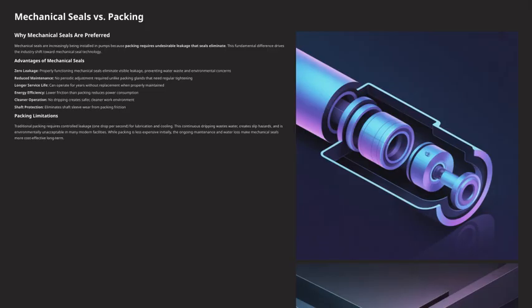It's also important to note that mechanical seals are not more tolerant of shaft misalignment. In fact, they require very precise alignment. They are actually more sensitive to issues like misalignment, vibration, and shaft runout than packing. So, proper installation and maintenance are crucial for their effective operation. In summary, while both have their roles, the industry is clearly shifting towards mechanical seals because of their efficiency, environmental benefits, and long-term cost savings, though they do demand careful handling and precise alignment.